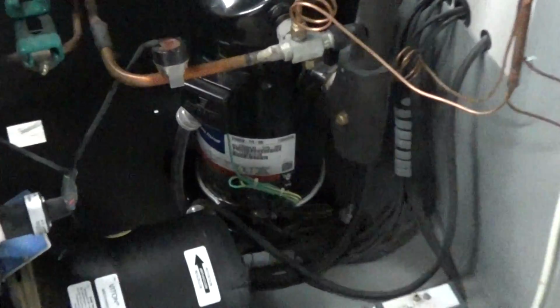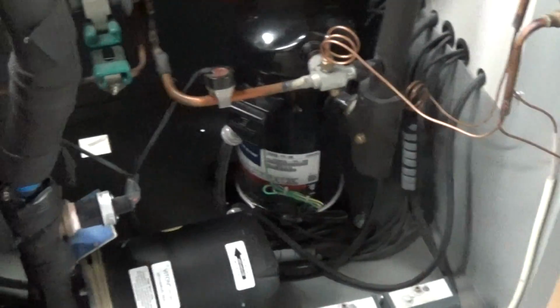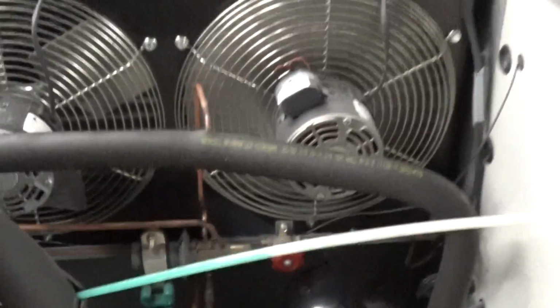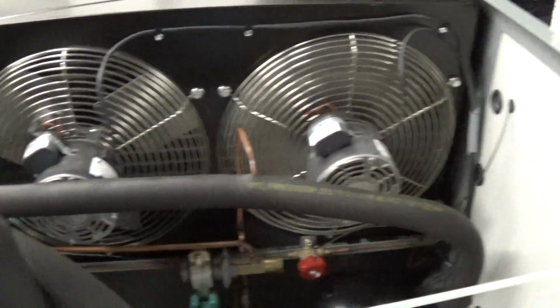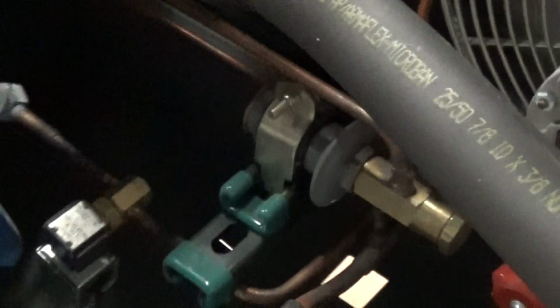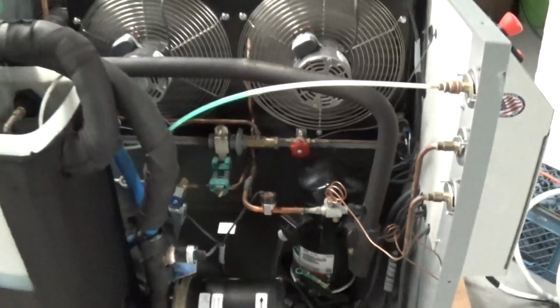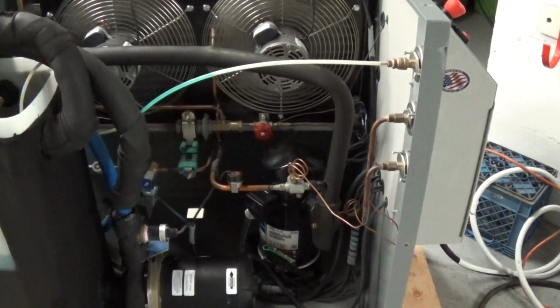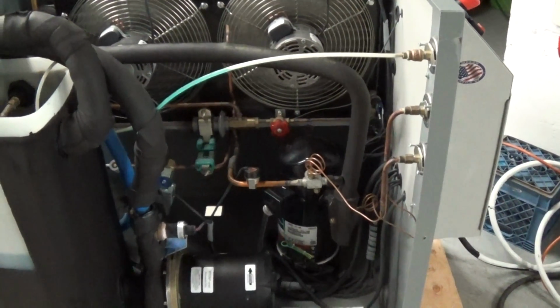This unit has technically, it's actually a 3 horsepower or a 36,000 BTU per hour Copeland scroll compressor. We have 2 cooling fans. You can see one just turned on, which is nice, so it's on demand based on two fan switches we have here. It's a nice little setup. It has a hot gas bypass there, and also a refrigerant cyclops, R407C, and also that's a liquid line solenoid valve for the refrigerant. This controls the cooling by controlling or cycling the hot gas bypass.